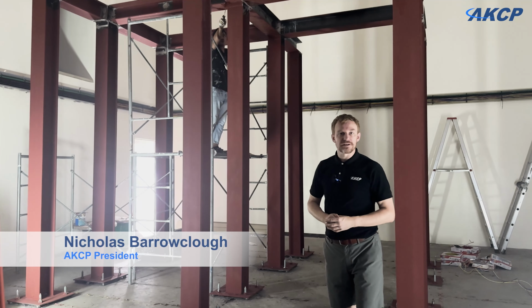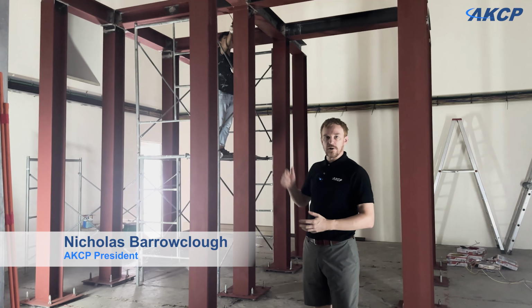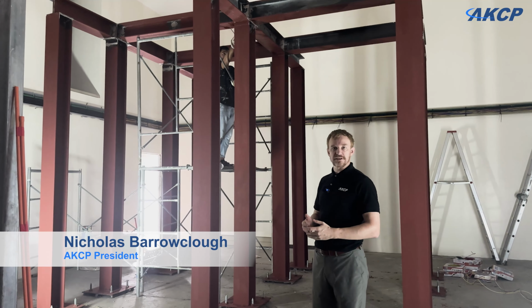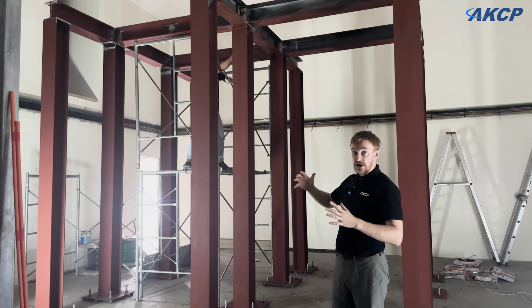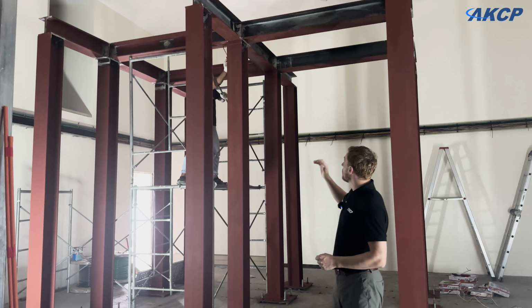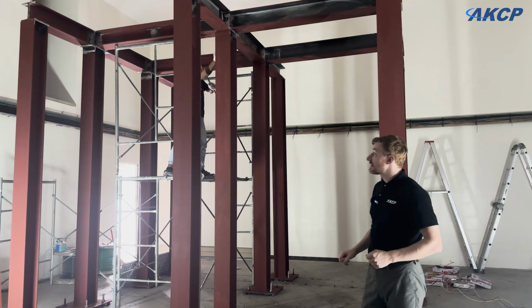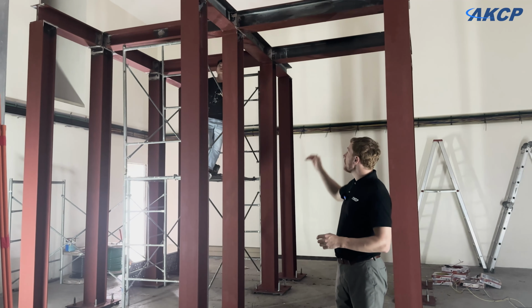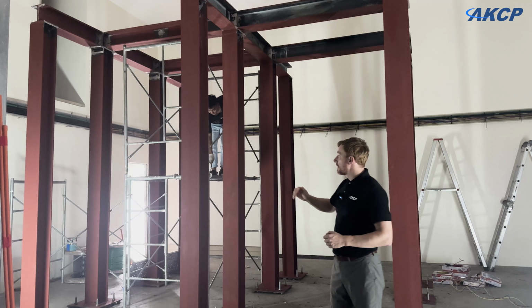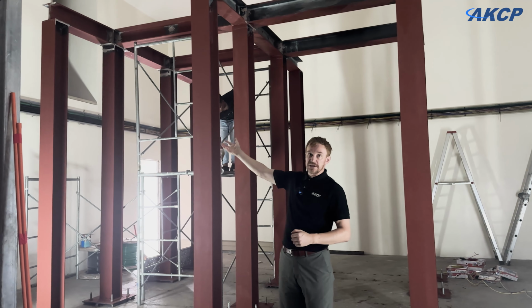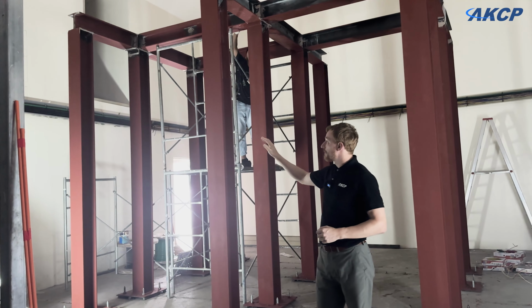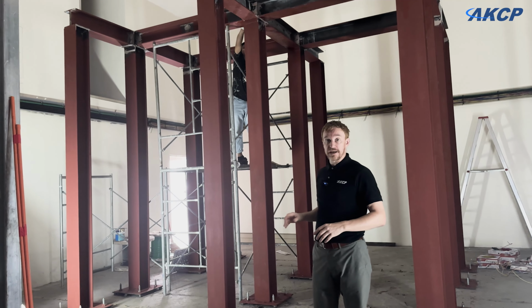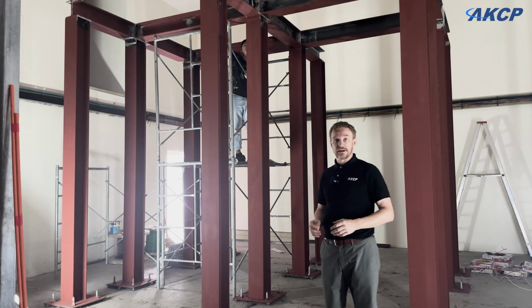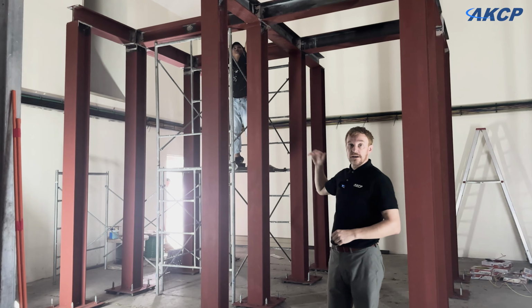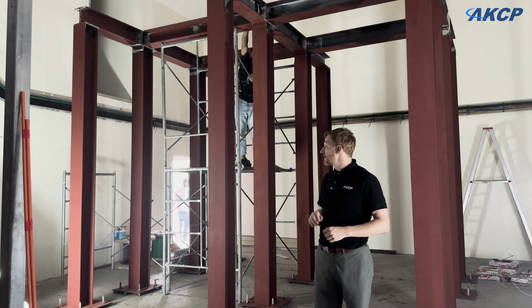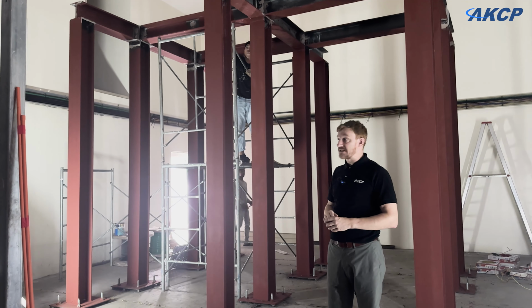Here's the progress now on the steel structure that's going to be holding up the overhead bus bars and water distribution pipes. The overhead heat exchangers are quite large and heavy and full of water, so that's why we've got such a sturdy steel structure here. It's relatively high because on the wall where the bus bars are coming from we're going to have glass panels, and we're a little limited in space. As this is a retrofit of an existing building, ideally this would have been shorter and we could have brought the bus bars in from another location, but we have to work with the space we've got.